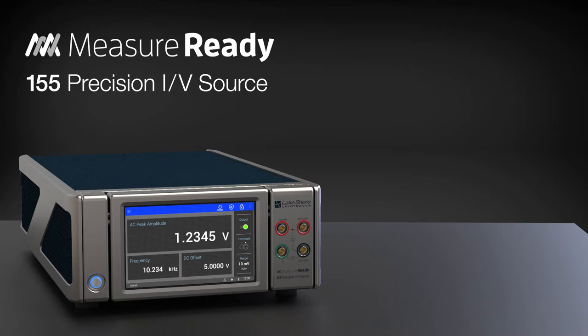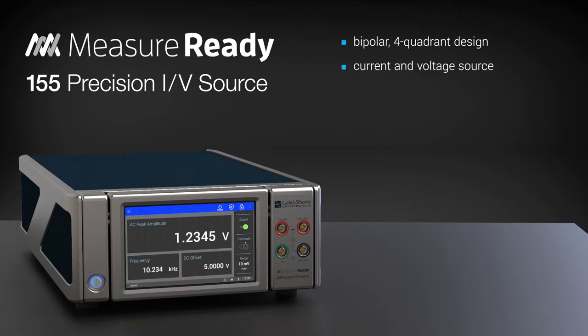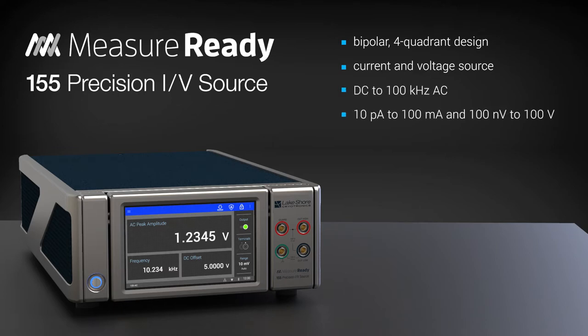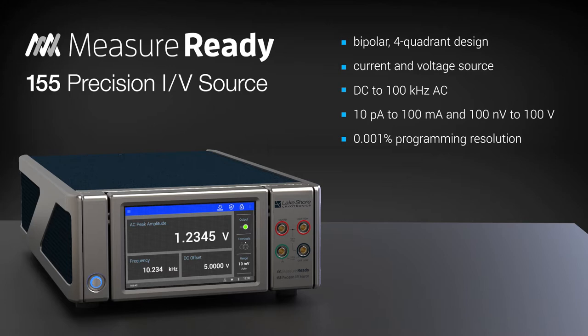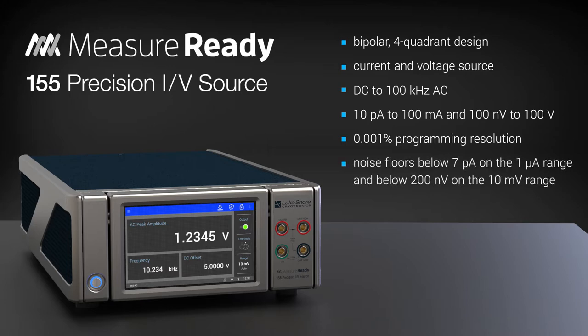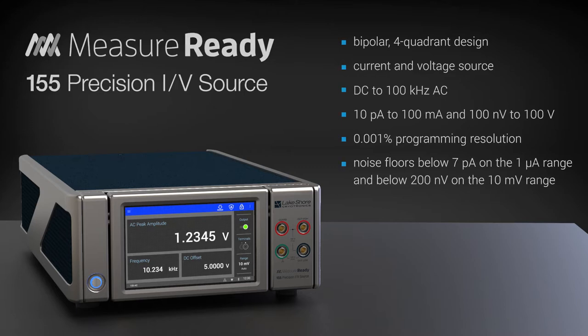The 155's bipolar, four-quadrant design delivers a stable source of current or voltage from DC to 100 kHz AC, ranging from 10 picoamps to 100 milliamps and from 100 nanovolts to 100 volts with 0.001% programming resolution. Noise floors are held to exceptionally low levels: under 7 picoamps on the 1 microamp range and under 200 nanovolts on the 10 millivolt range without requiring external filters.